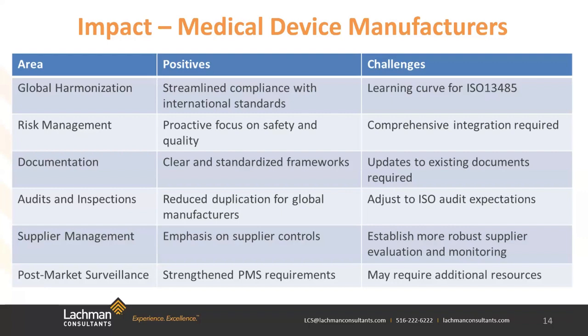The documentation requirements have a positive impact in that ISO 13485 provides a clear framework for documentation, making it easier to demonstrate compliance during inspections. However, manufacturers will need to update their quality manuals, their risk management files, and other documentation to ensure that they're meeting ISO 13485. From a supplier management perspective, the positive is that supplier controls will ensure better oversight of components and materials, reducing potential quality issues.